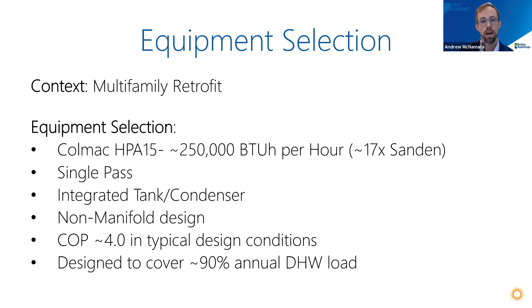Moving on to the next slide, here are the technical specs. We used a Colmac HPA15, which is 17 times the size in terms of capacity of an individual Sanden unit. So no more manifold of many units tied together, and a hybrid plant design where we reused the existing boiler. The heat pumps were designed to cover about 90% of the annual domestic hot water load.